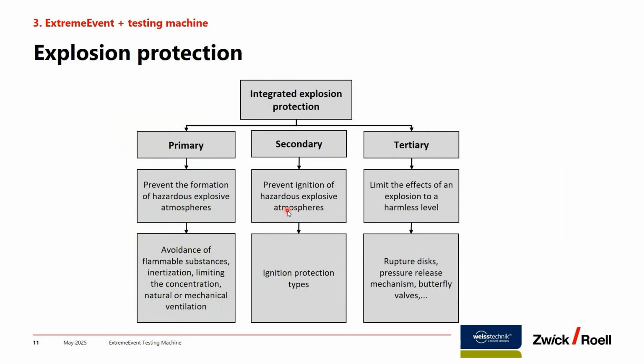As I mentioned, the extreme event chamber is a new innovation in the product portfolio of Weiss Technik. This is the first test chamber with this stationary explosion protection from Weiss, and this chamber is specially designed to withstand frequent explosions, so you can do more or less daily explosions.